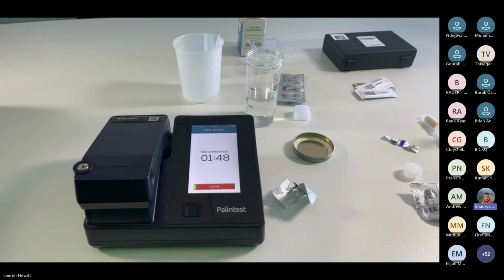Again, users don't need to be aware of this. They need to simply follow the instructions and get the result on screen. But I thought it would just be good to explain what is actually happening here. So the arsenic sensor uses an electrochemical technique to measure the concentration in water. Now this uses a single-use disposable sensor. So again, these sensors, once used, cannot be reused. They must be discarded, and you need a fresh sample and a fresh sensor for every test.